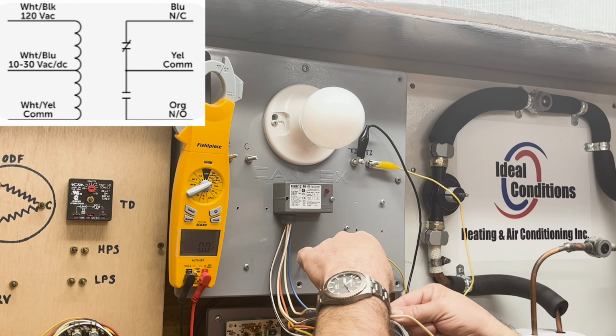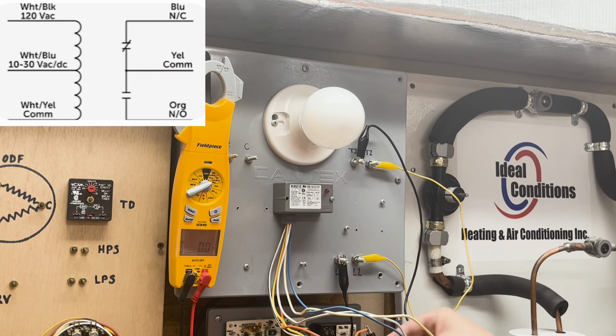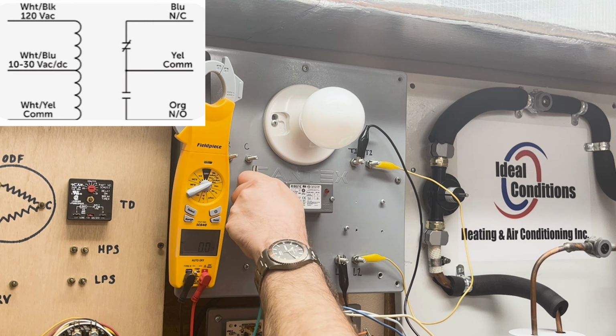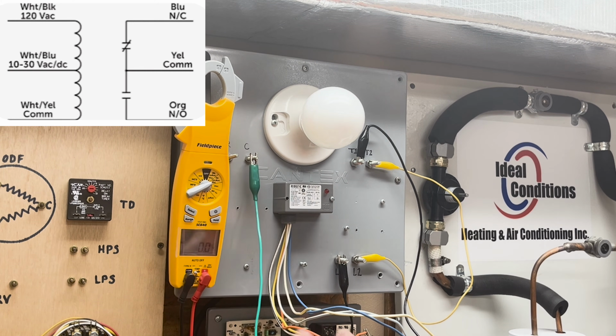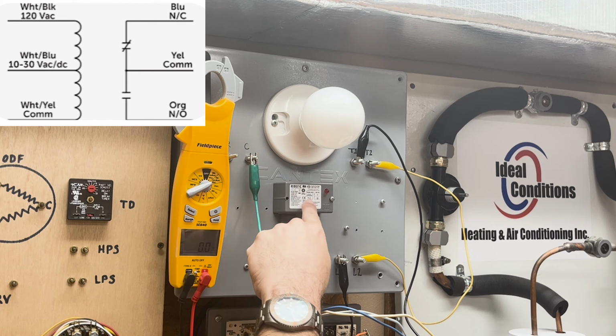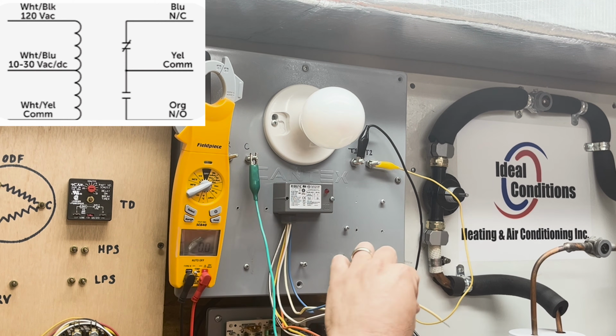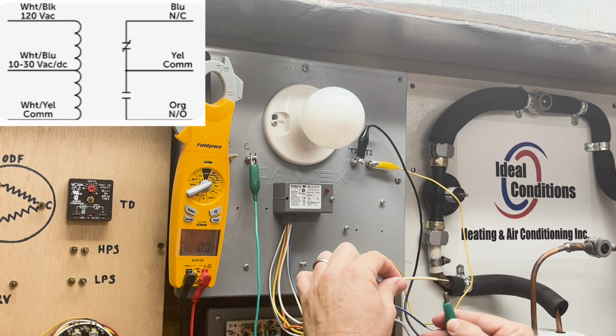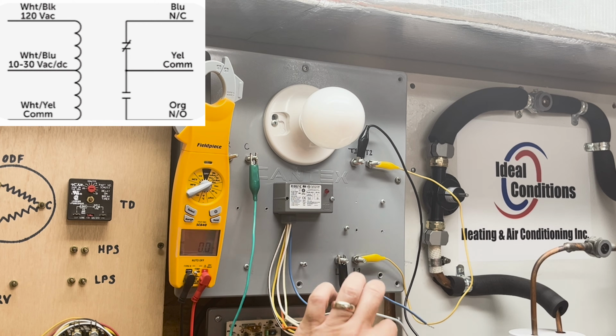and we're going to apply this to orange for normally open. All right, I'm going to put 24 volts back on the relay. This is how you would traditionally wire this for your blower relay. So we're going to take our common. We're going to go back to white/yellow, which is common. Here's white/yellow. We're going to go ahead and connect common there.